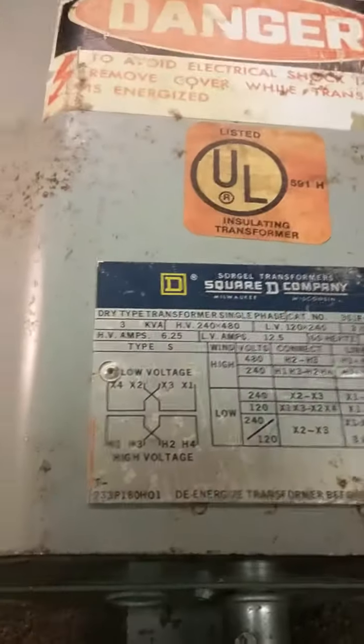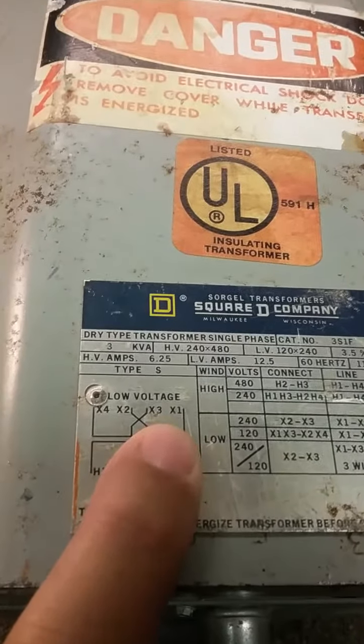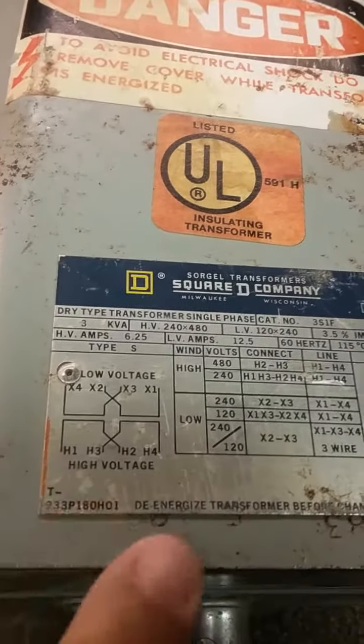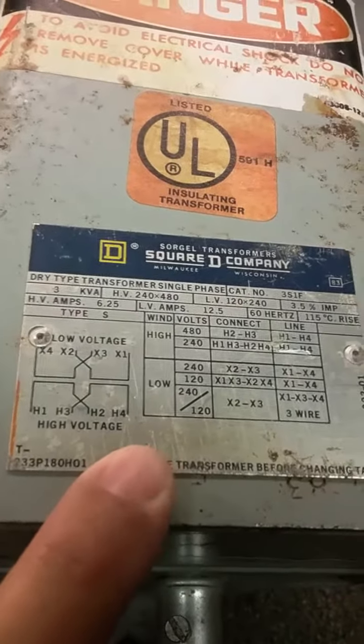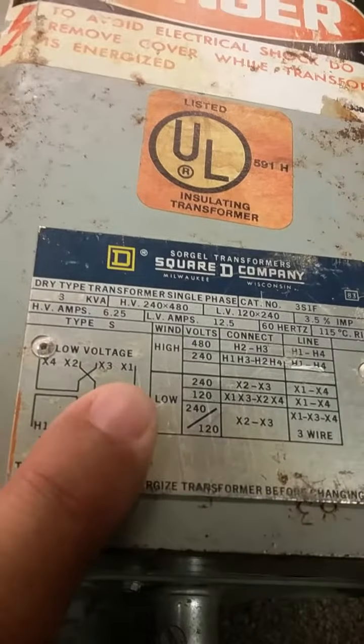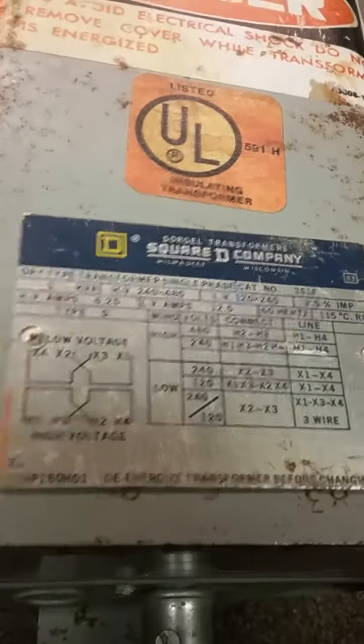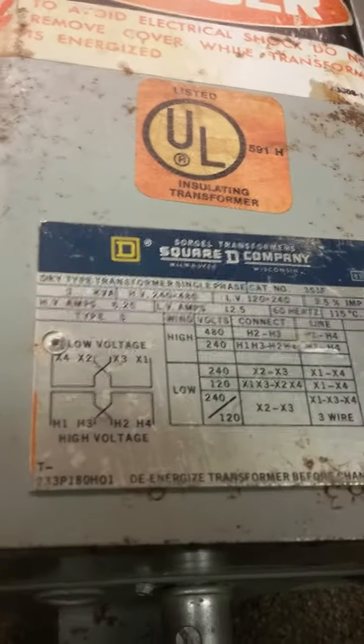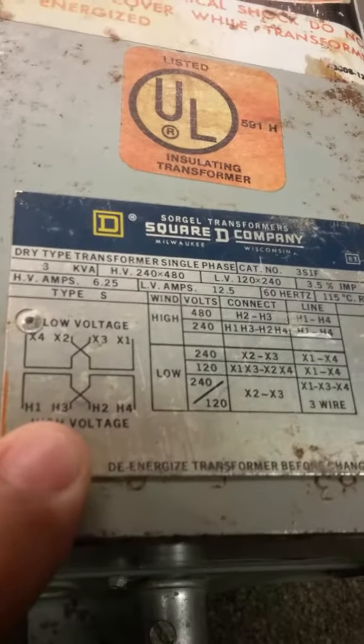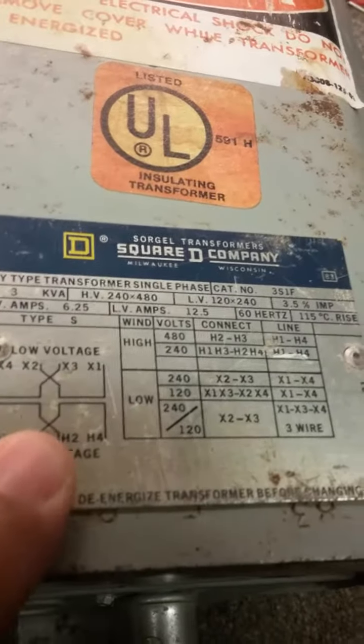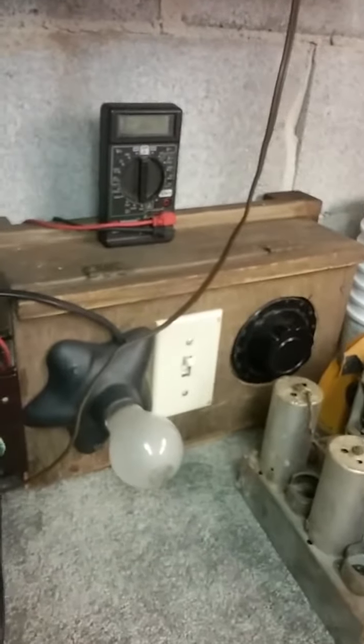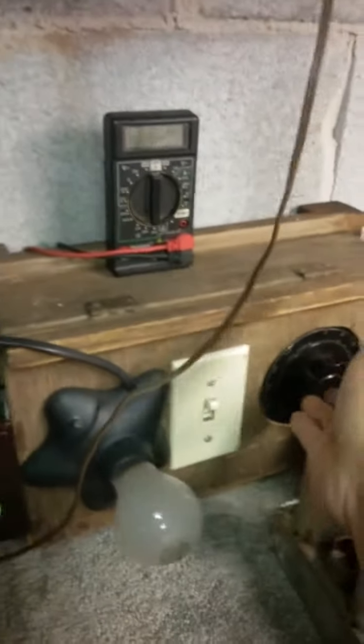So what I'm going to do to even test it, the first thing we're going to do is check the coils individually. We're going to check all 4 coils, X1 to X2, X3 to X4 on the secondary, H1 to H2, H3 to H4 on the primary, make sure that all 4 coils are working, that they're not shorted or open. And we'll check them with a simple ohms meter. Then to check the voltage drop and make sure that this is putting out half the input, I'm going to use my little box here, which has a VAC, and it also has a light bulb option for current protection, which I can throw on and off with the switch.